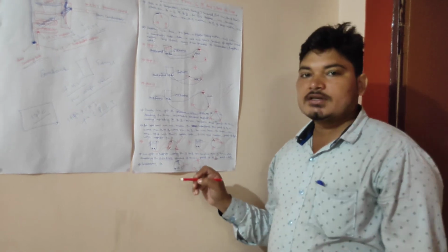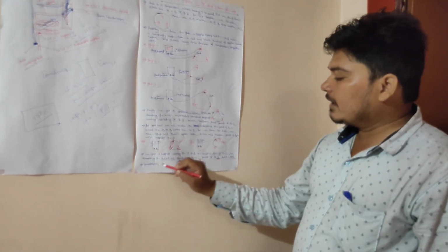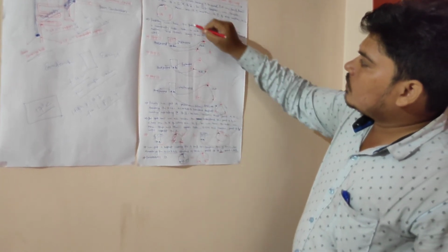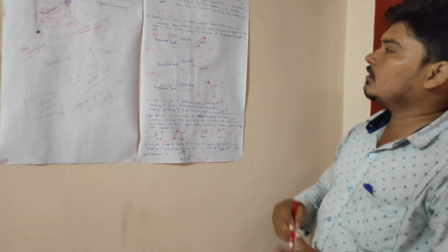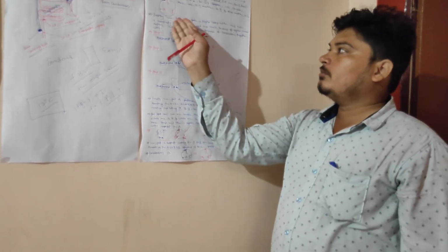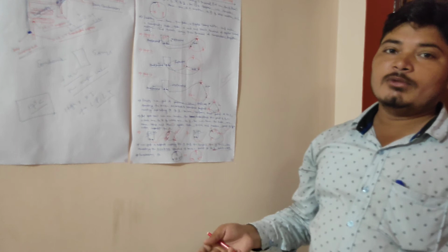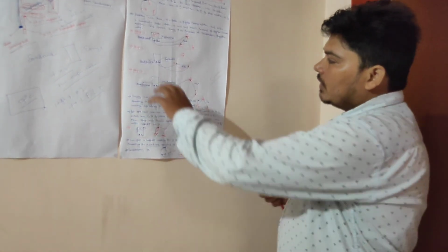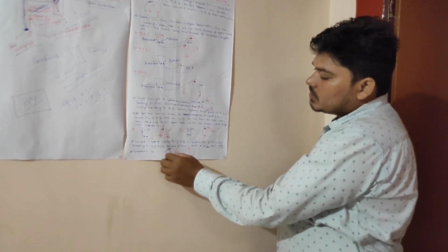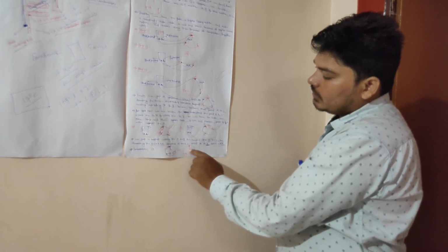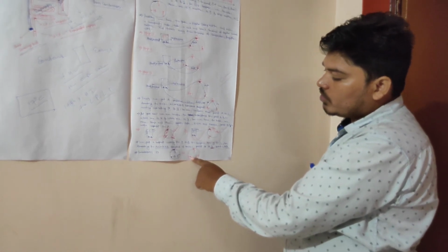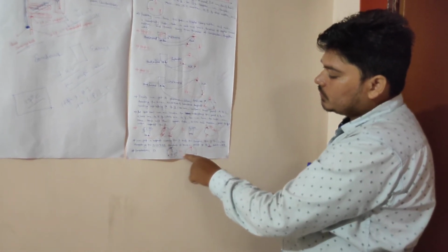So finally calculation, the picture will be like this, and go to the first picture which I drew like this. This is a compressor which having 3 electrical terminals A, B, C. We don't know which one is common, which one is running, which one is a starter. Finally, according to this process, we get a picture like this. This is point A. It is similar to the common point. This is point B. It is similar to the starter point, and this is point C. It is similar to the running point.